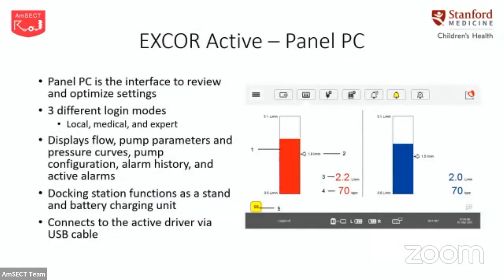The panel PC is our new change from the integrated laptop. So this is, like I mentioned, a touch screen where you review and optimize your settings. You do still have to log in like you did with ICUS, but there are 3 different modes you can log in as. So you can be local, which is basically a display only of your pump flows and your pump pressure curves.